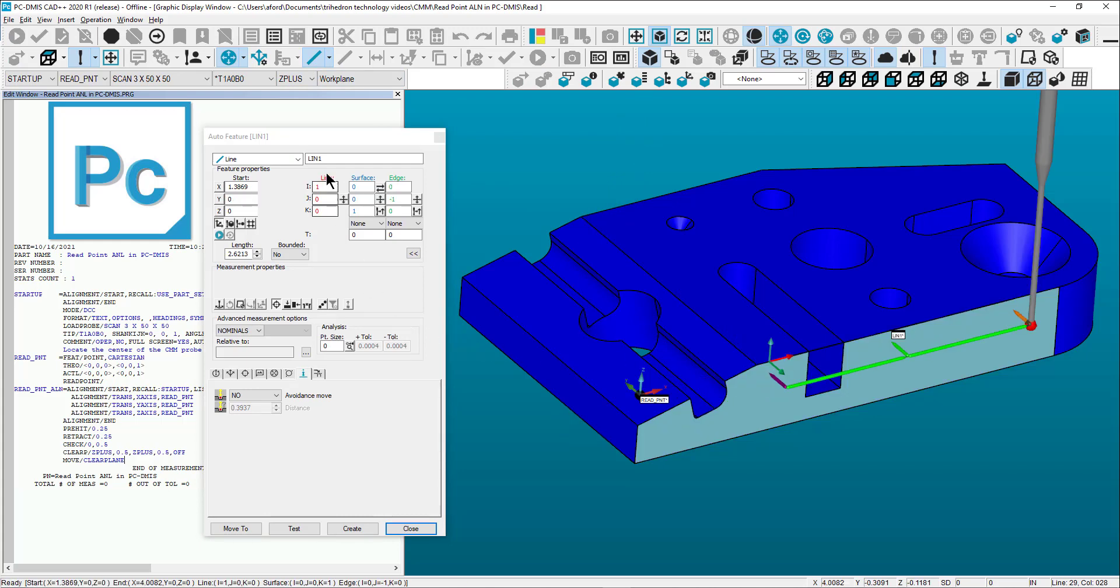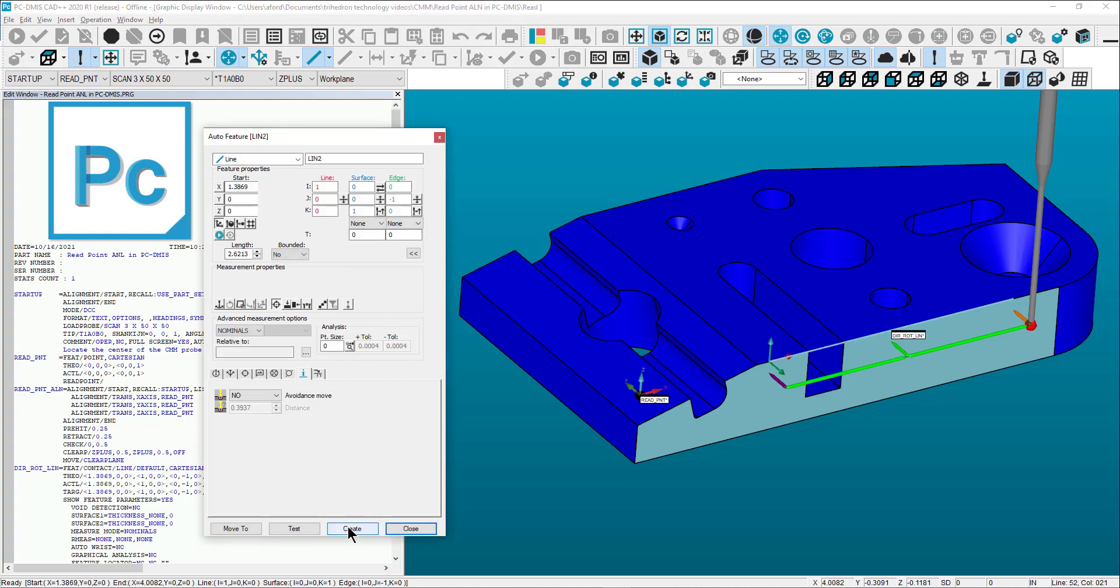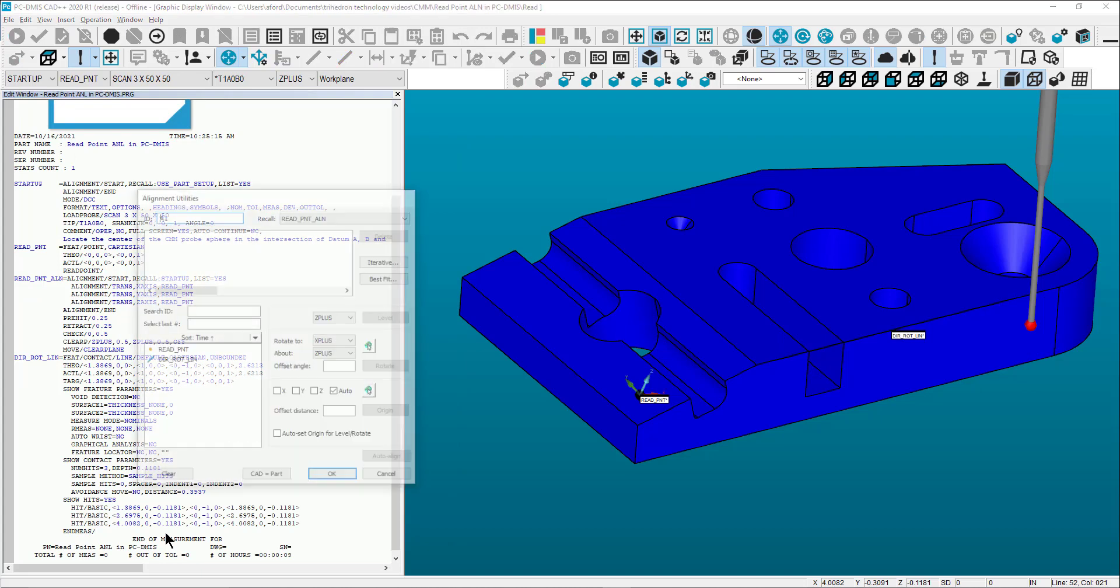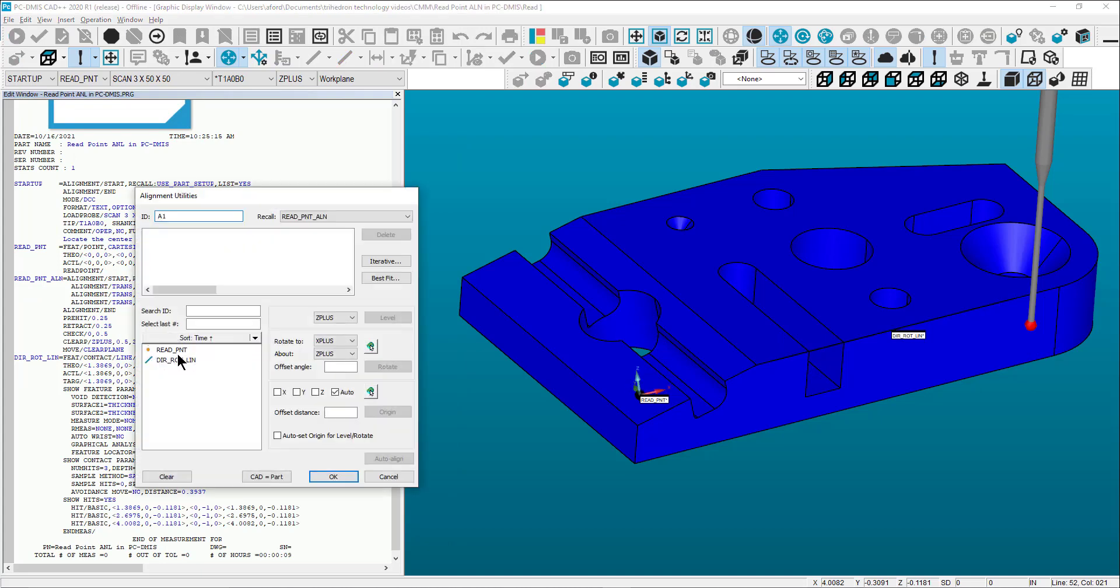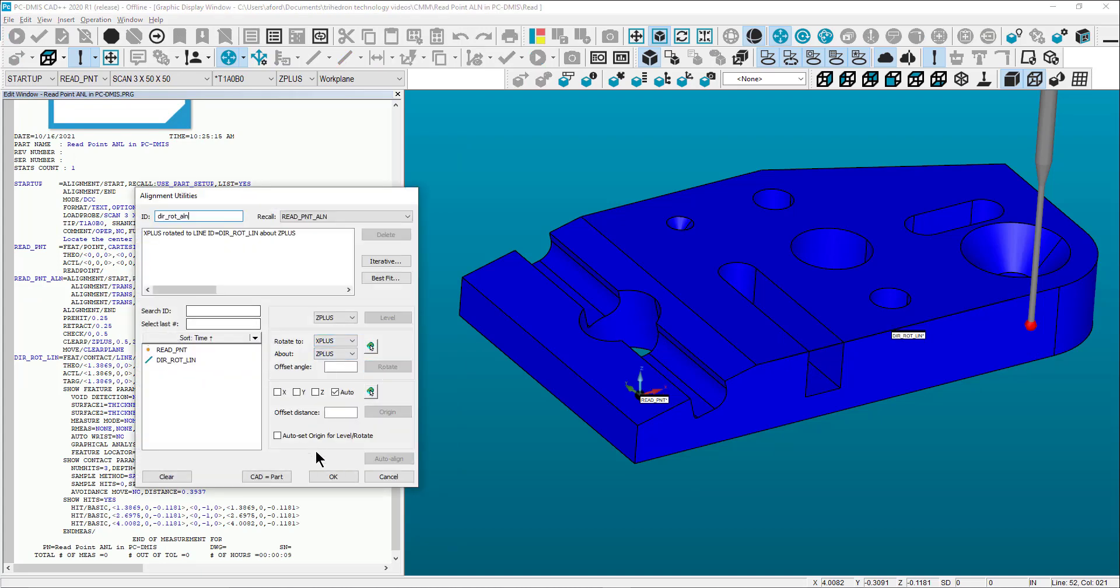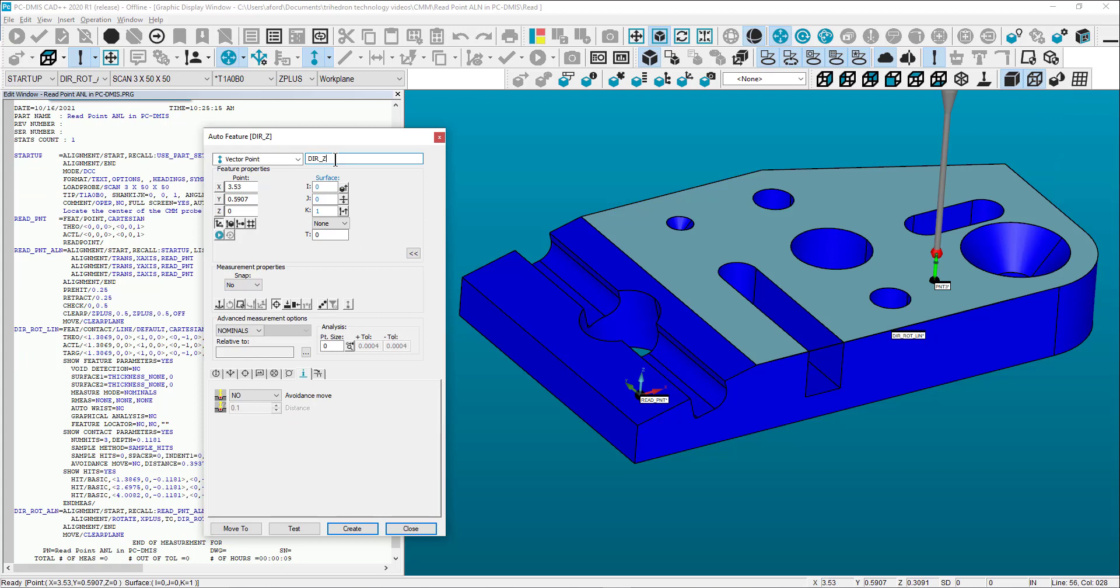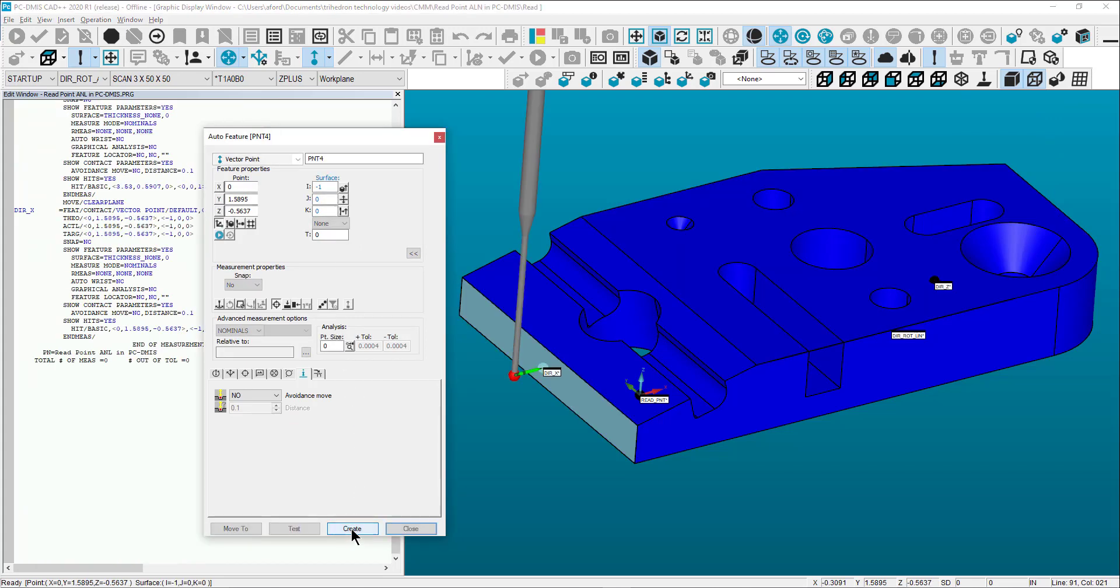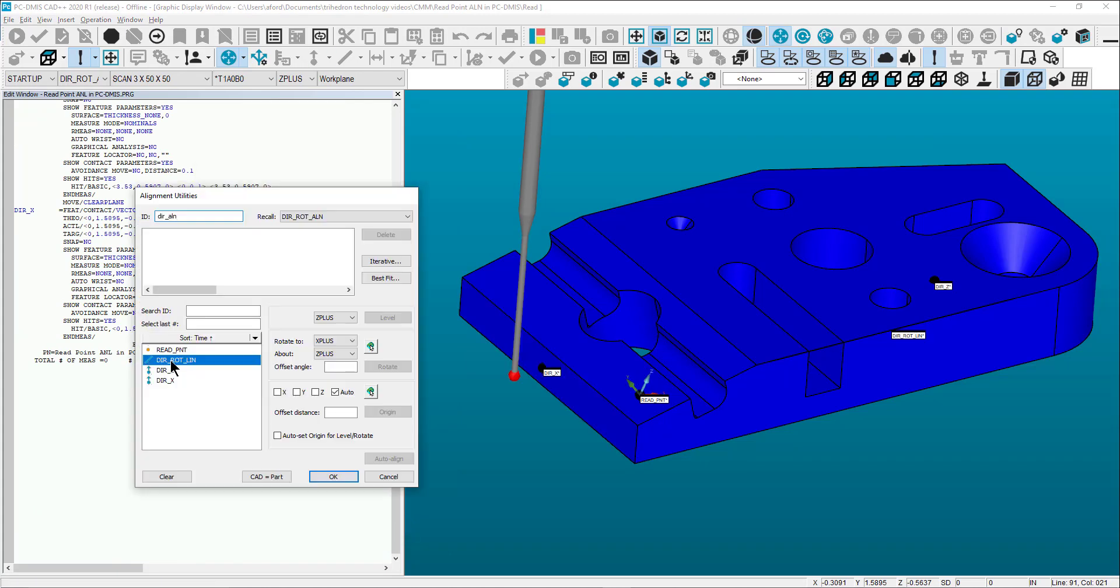Create a line feature to be used in a dirty rotation alignment. In this case, the part is true enough to the machine axes that we can finish off our dirty alignment with vector points. The intent of this alignment is to get the CMM roughly aligned to the workpiece.